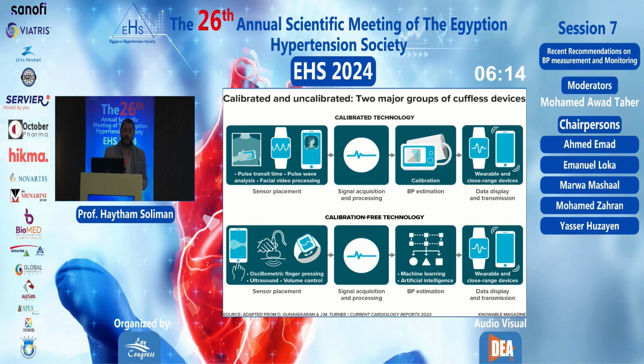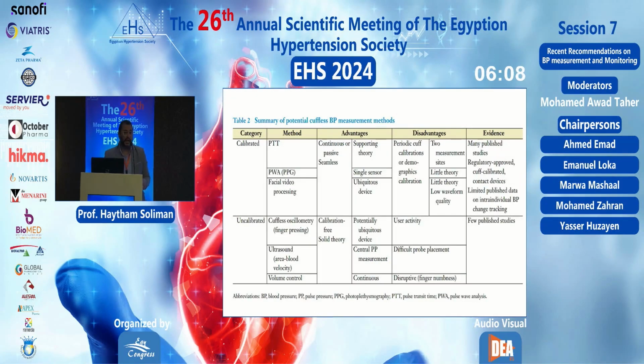So the calibration, non-calibration or calibration-free aspect is inside the device itself. We see that calibrated devices have more data and more accuracy in the literature than calibration-free devices, because they have a reference inside the device, and do not depend entirely on machine learning. In machine learning, if you give a wrong input from the start, the cascade of machine learning will augment this wrong information to give a continuous fallacy in the readings.